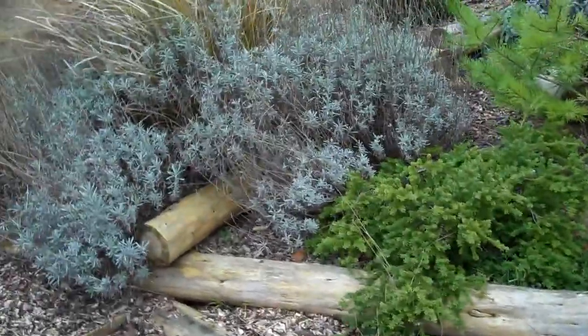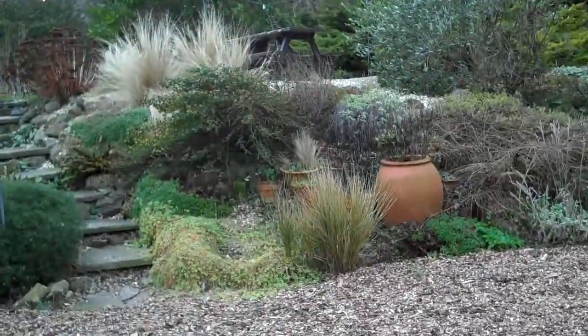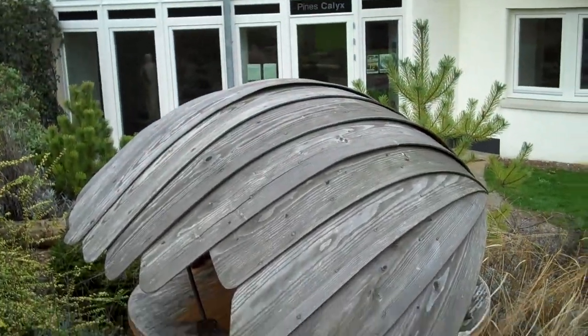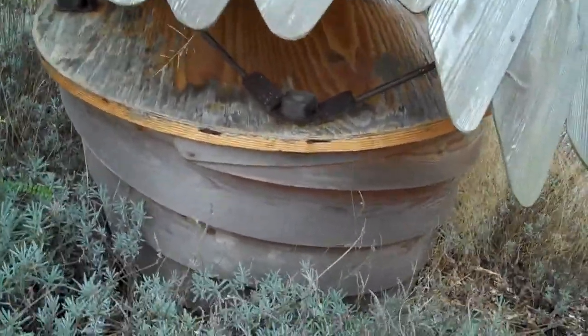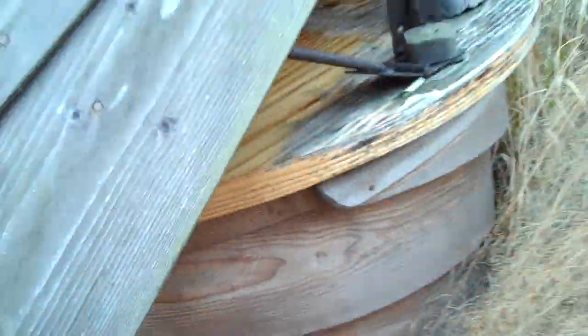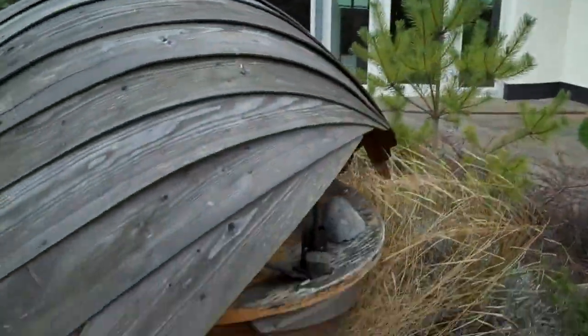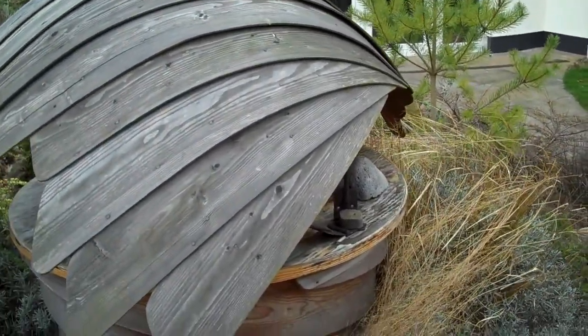Is this a herb garden? It's partly herbs, other plants and some little vines up there. Just walking past, this is actually an artistic intervention on top of an inlet to the earth tube — it's drawing in air at low velocity through those gaps. There's a 30-metre long tube going right round the back of the building, which draws in all our fresh air so that it's pre-cooled in summer and pre-warmed in winter — it's a constant 12 to 13 degrees centigrade. So it looks like just a sculpture but it's actually the ventilation system — hiding the ventilation system — and it's nature's ventilation system.